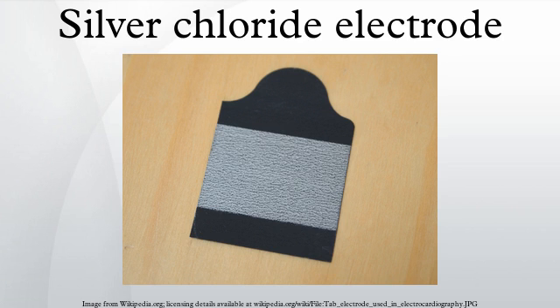At the same time, the chloride ions, which are anions in the electrolyte, travel toward the electrode and are oxidized as they bond with silver of the electrode, resulting in silver chloride and free electrons delivered to the lead wire. The reaction allows current to pass from electrolyte to electrode, and the electron current passes through the lead wire for the instrument to read. When there is an uneven distribution of cations and anions, there will be a small voltage called half-cell potential associated with the current. In the DC system used by ECG and EEG instruments, the difference between the half-cell potential and the zero potential is shown as DC offset, which is an undesirable characteristic.